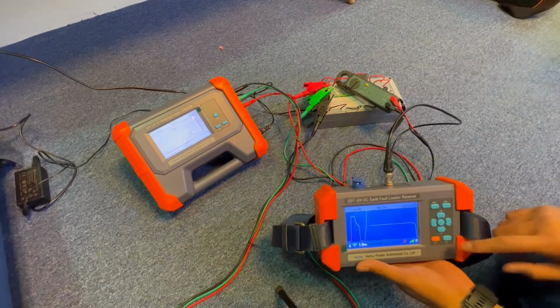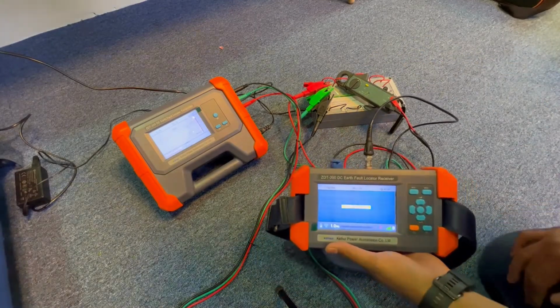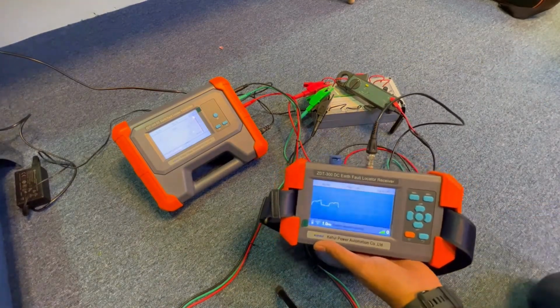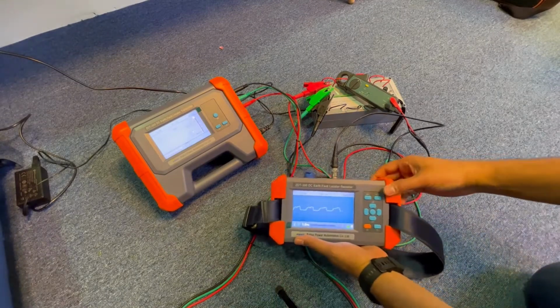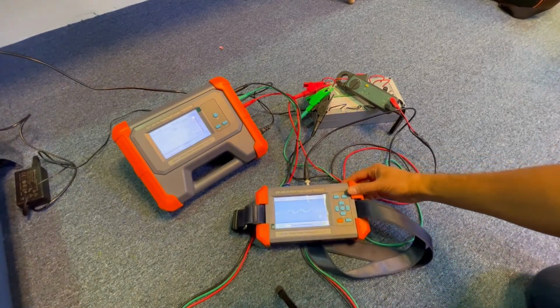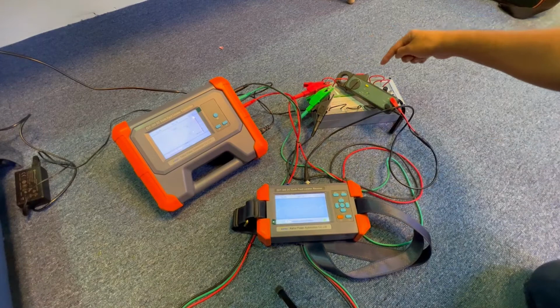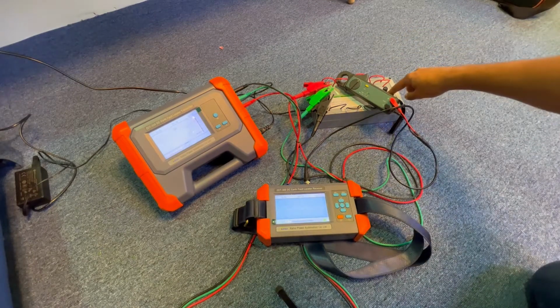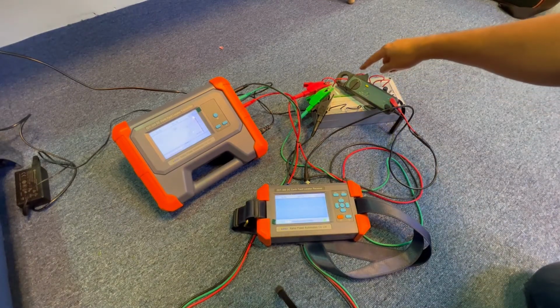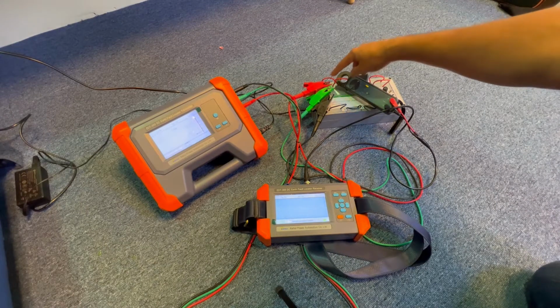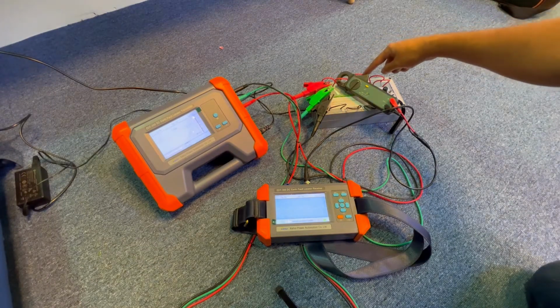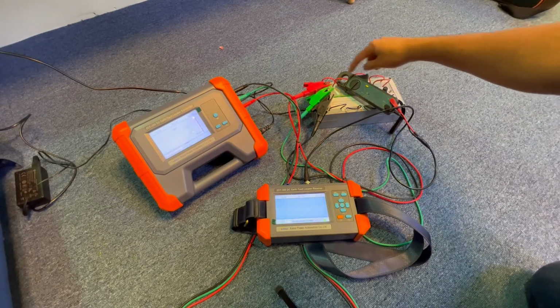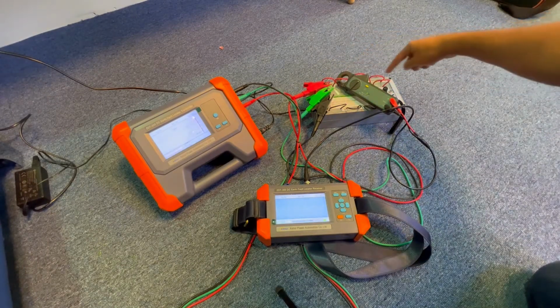So we are going with feeder 1. Always refresh when you connect to a different feeder. So the fault is in feeder 1. This is a loop connection. So we have created a fault at +4. So the signal should show until this loop 1, 2, 3, 4. So if I create a fault here only in 1, the fault should be only in 1. It should not be in others.